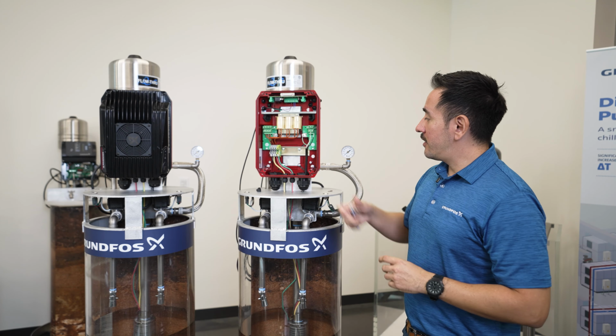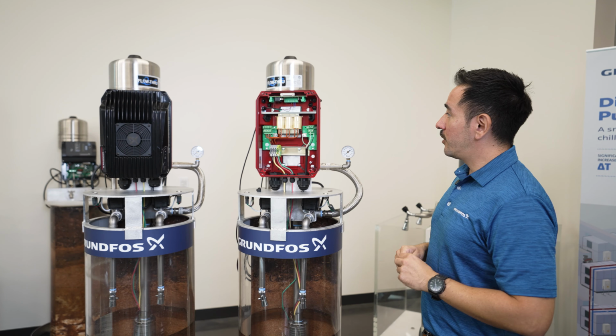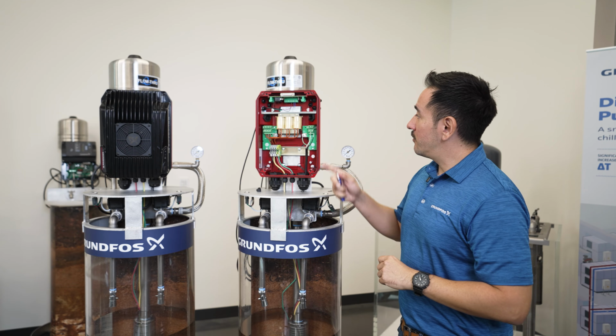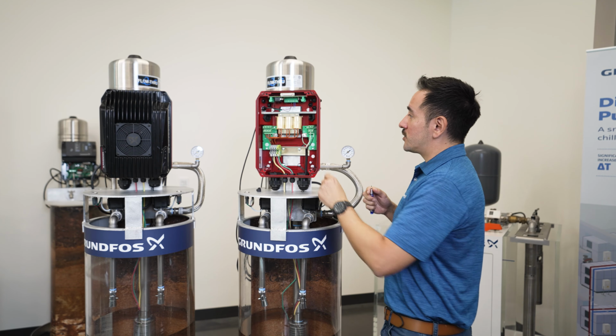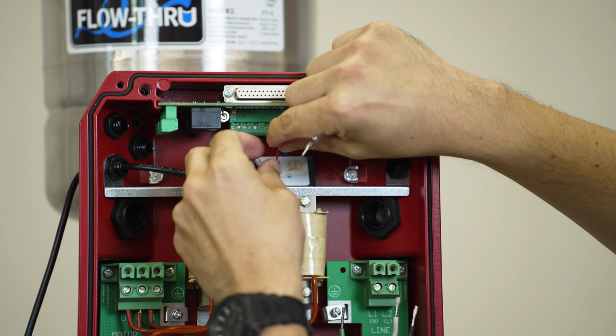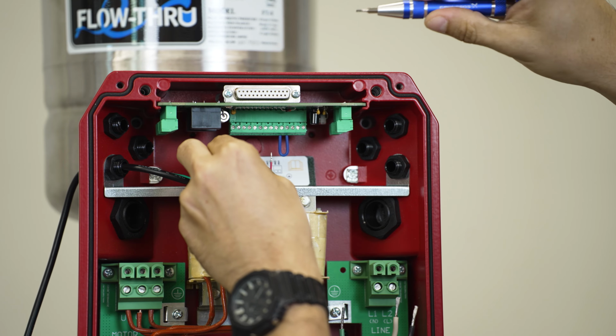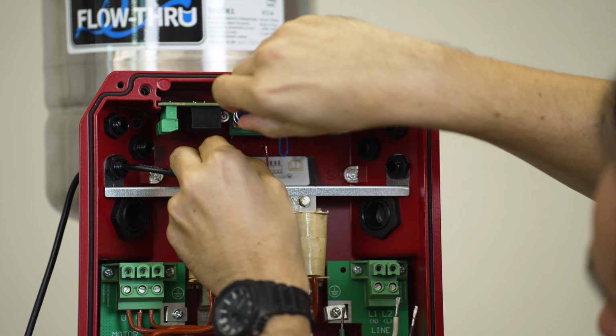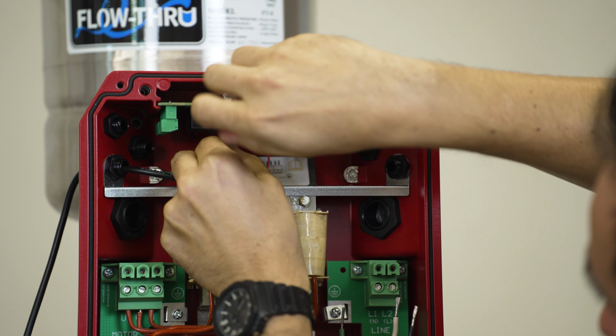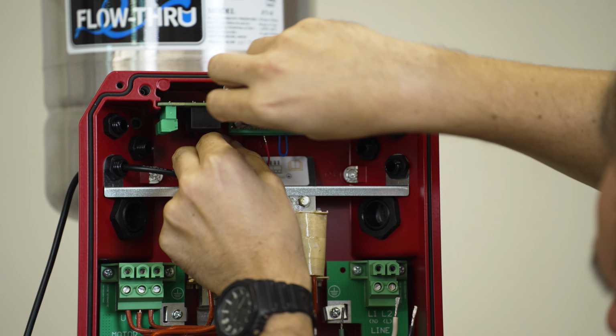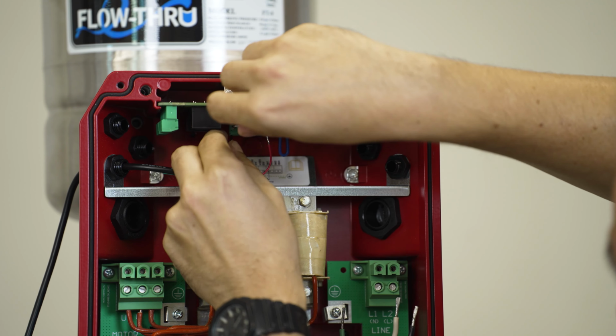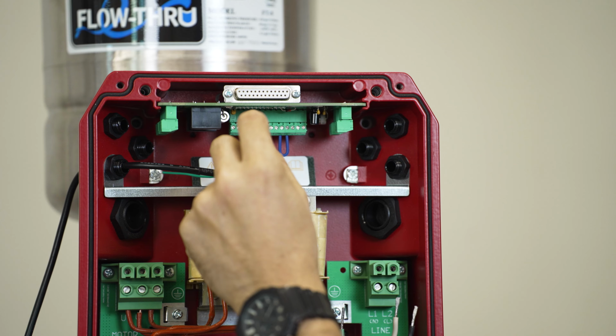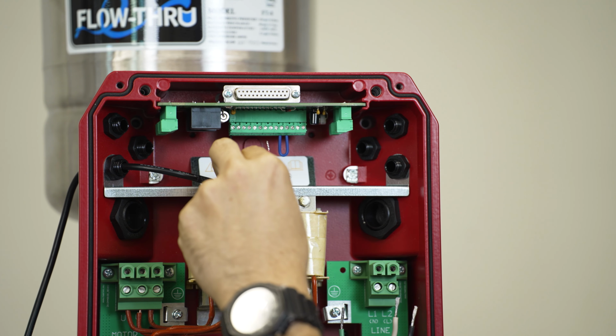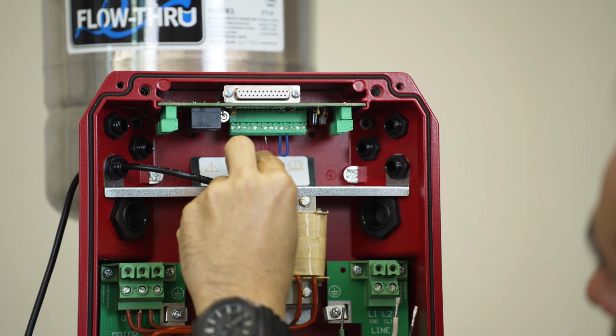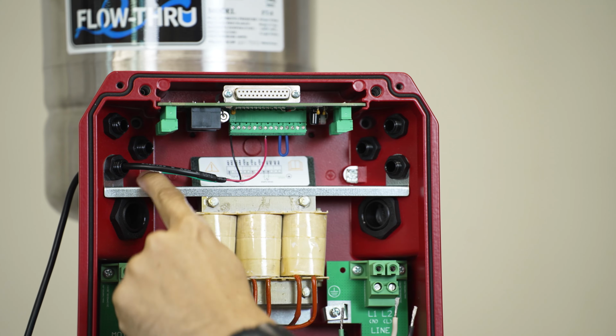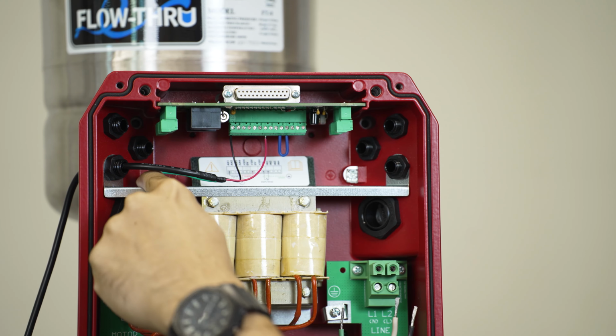Now that we have installed the motor wires into their correct terminals, we will move on now to installing the pressure transducer wires, which will go up in these terminals up here. So for your transducer wires, you will have 3 wires. You will have your signal, your power supply, and you will have your earth or ground wire. Your signal will be connected to the first terminal, which is analog input 1, and your supply wire will be connected to the terminal labeled 15 volts, which will be your 7th. And then your ground will be connected to your earth terminal.